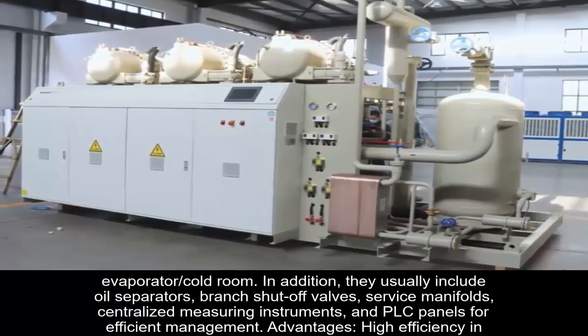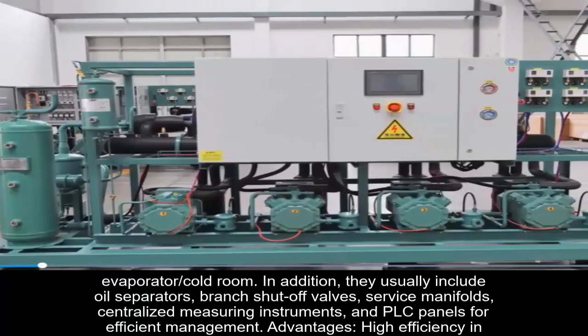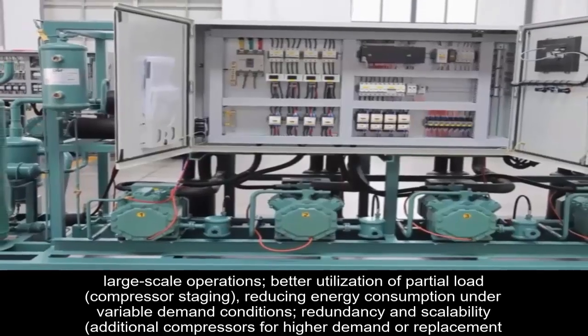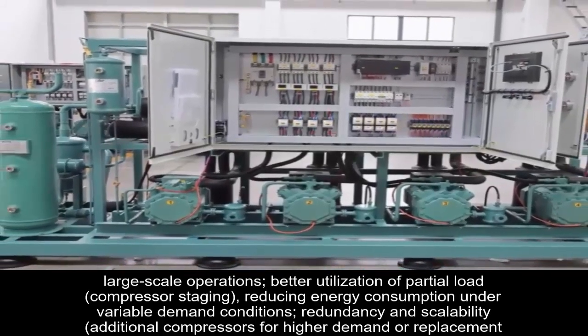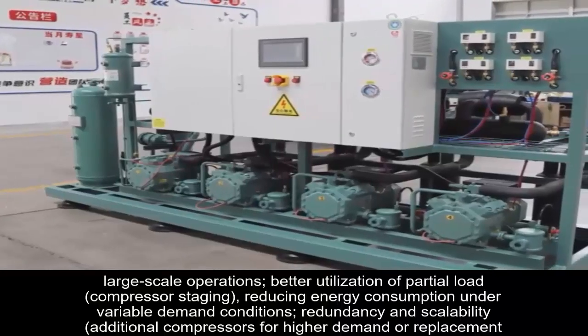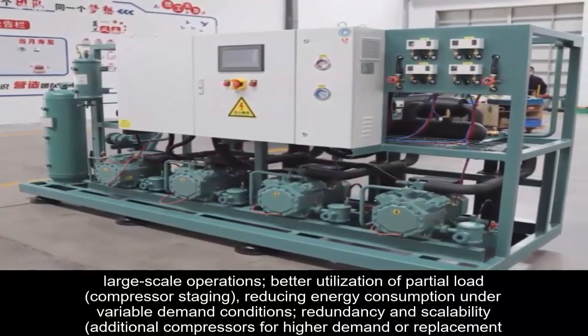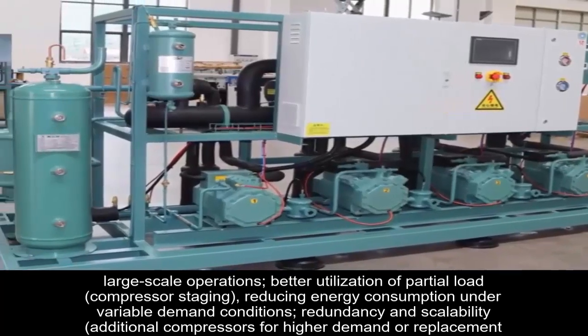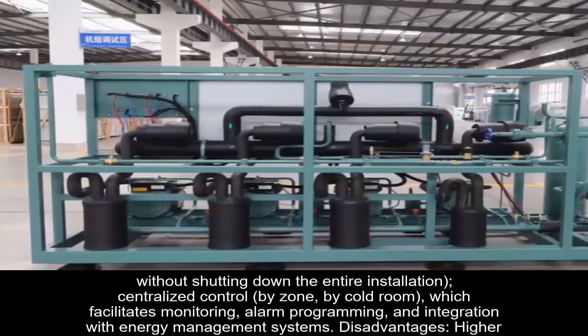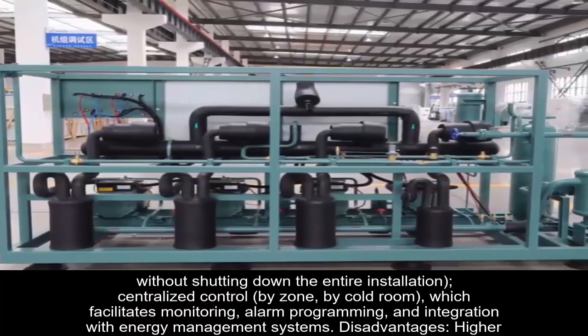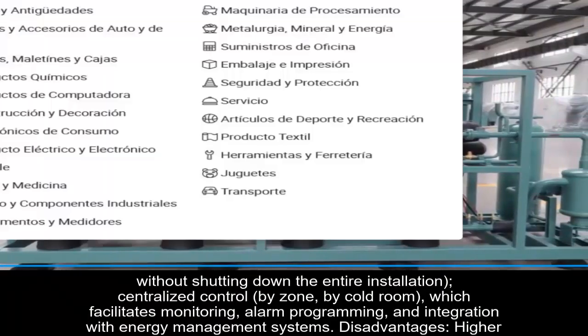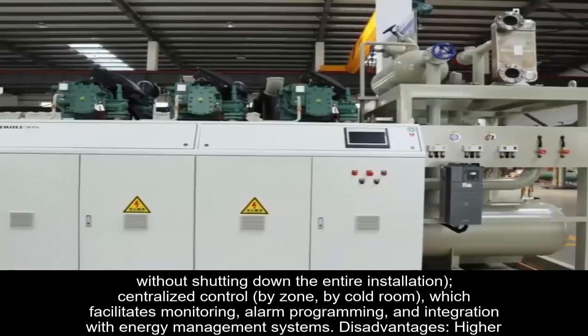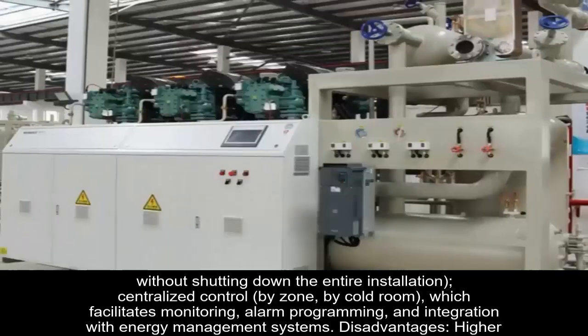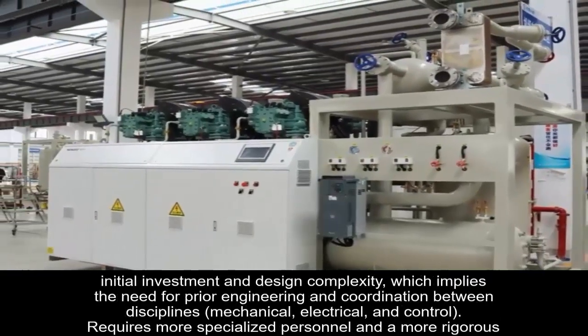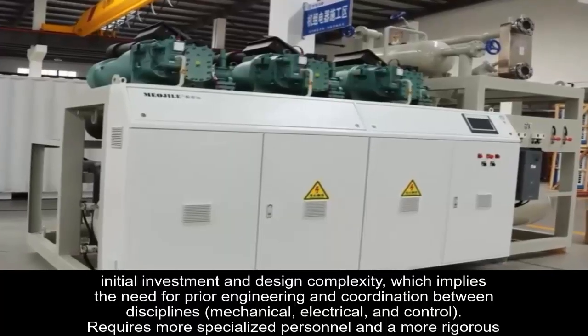In addition, they usually include oil separators, branch shutoff valves, service manifolds, centralized measuring instruments, and PLC panels for efficient management. Advantages: high efficiency in large-scale operations, better utilization of partial load, compressor staging, reducing energy consumption under variable demand conditions, redundancy and scalability, additional compressors for higher demand or replacement without shutting down the entire installation, centralized control by zone, by cold room, which facilitates monitoring, alarm programming, and integration with energy management systems.